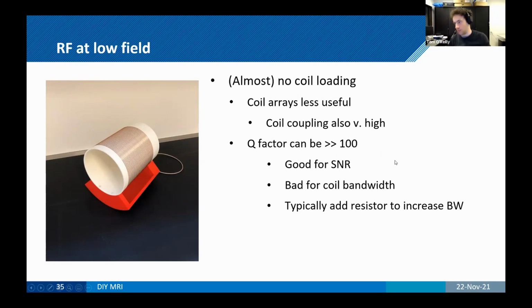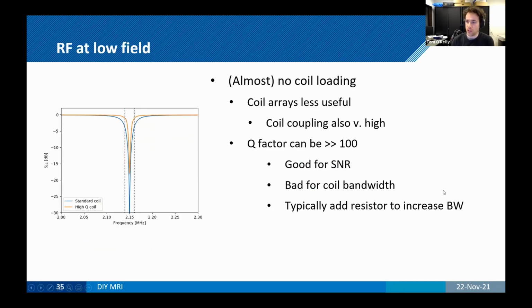Your Q factors can be way higher, which is good for SNR, because your SNR scales with the square root of your quality factor, but it's terrible for your coil bandwidth. So the coil bandwidth will decrease with 1 over Q. So actually, to deal with this, we typically add a resistor to our coil to increase the bandwidth, knowing that that's going to reduce the SNR that we get. But if we don't do that, we just cannot acquire signal outside of our bandwidth.